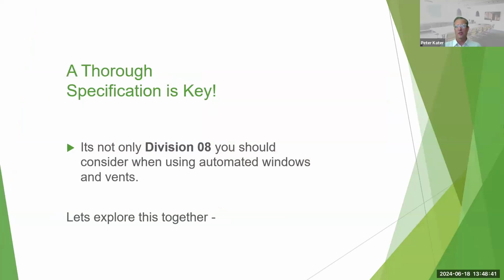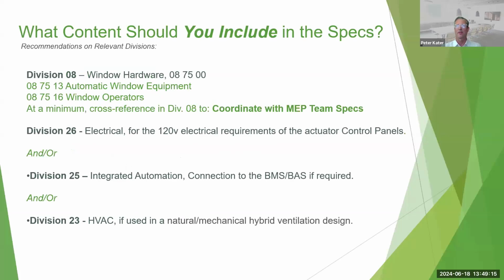The specification document is key in designing a building with natural ventilation. And although the hardware for the natural ventilation system is typically described in Division 8, which is the openings division, there are other divisions that relate to other aspects of the natural ventilation system, which need to be included or have content added to them so that the system is properly specified. So, as I mentioned, Division 8 is really where the hardware lives, and the window controllers typically live here.